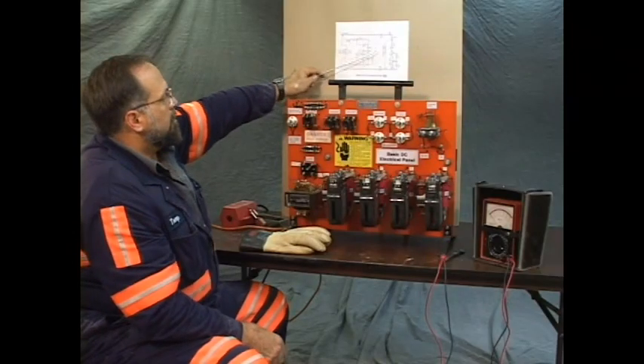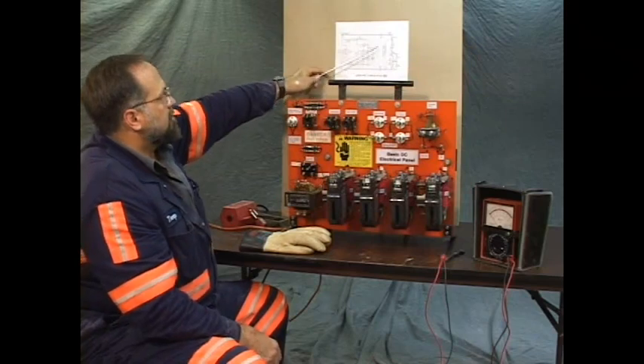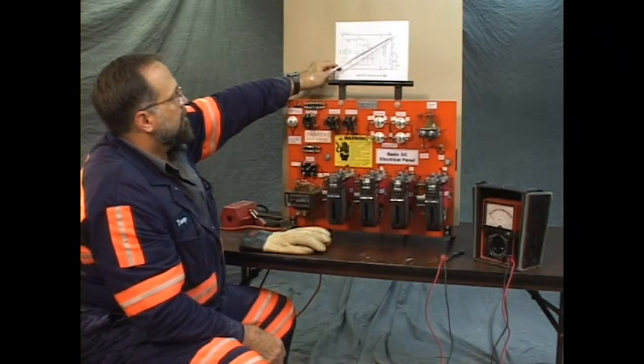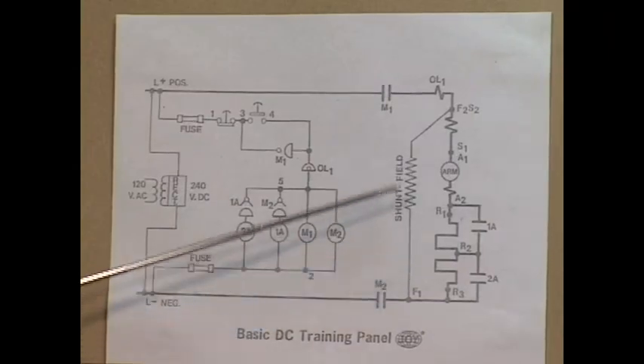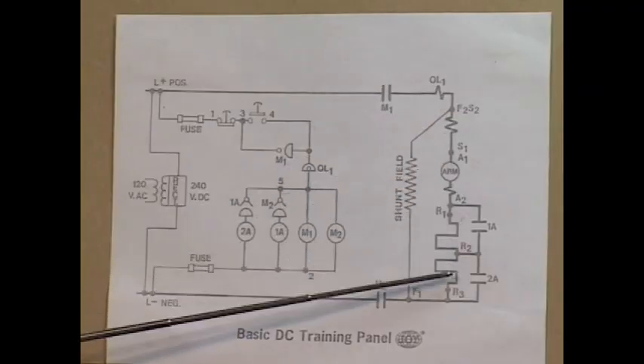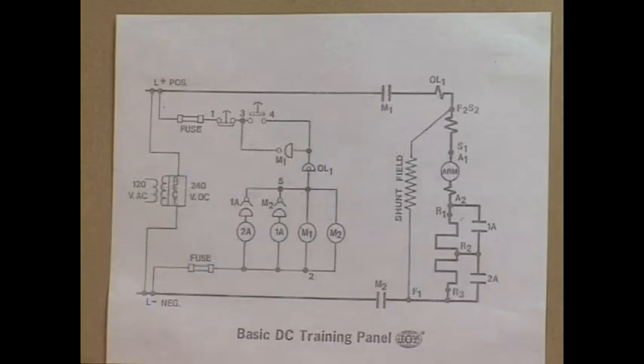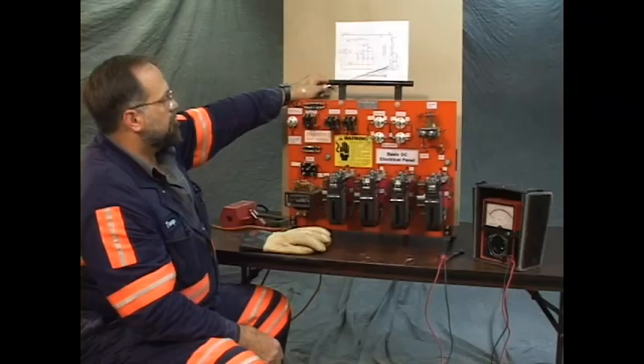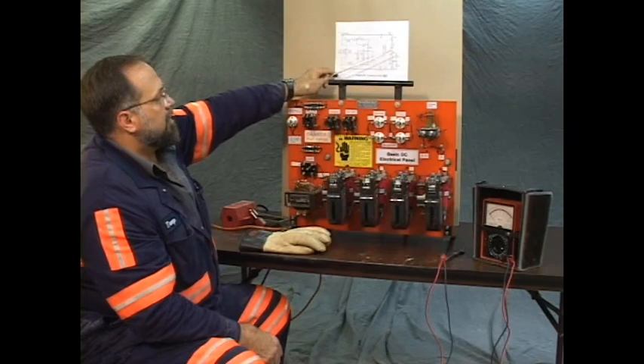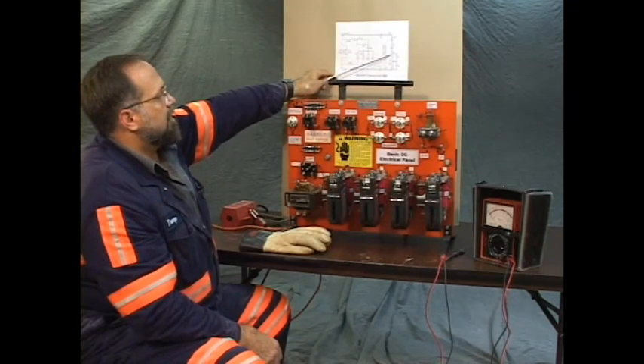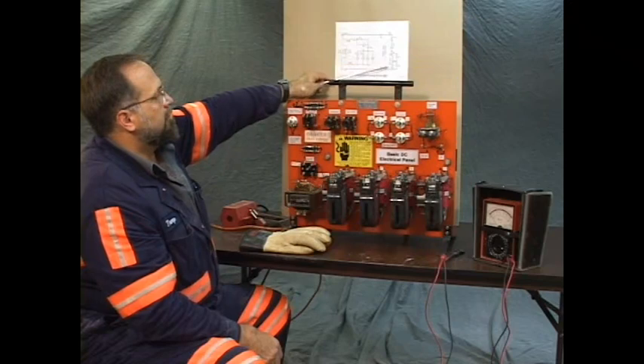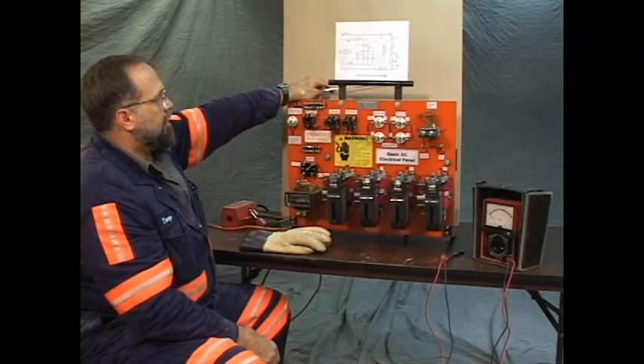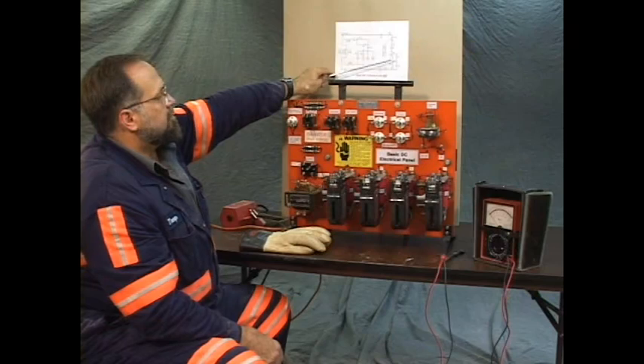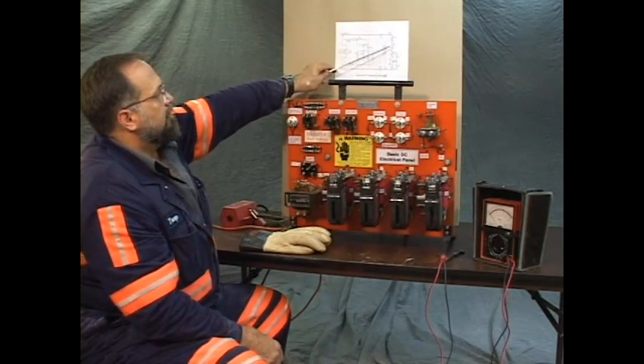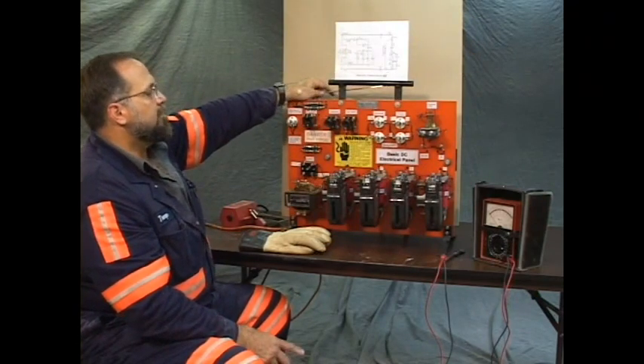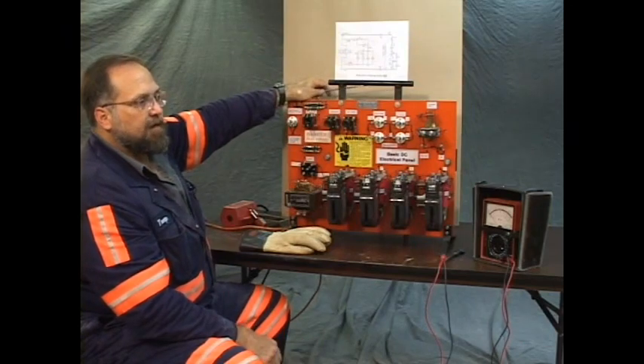Ideally, when M1 and M2 close, the main contactors, positive and negative, you should have a circuit that would energize the shunt field, the armature, the resistor between R1 and R2, the resistor between R2 and R3. Then after an interval, 1 second, 1A closes. This light would go off, this one would be brighter, and this one would be brighter. After 1 second, 2A would close. This light would go off. The armature would be very bright. The shunt field and the armature would be the same intensity, the same brightness, and have the same power on them.